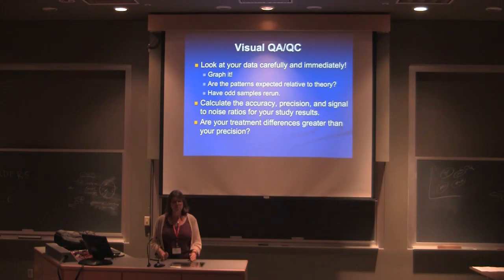Don't let it pile up, particularly if you're running your own samples and you get to be on the mass spectrometer only for a limited amount of time, and you're burning the midnight oil and you're getting the data off and you're just going to look at it later. And it piles up and piles up, and then finally you're all done, you're exhausted, and you go look at your data and it's like, oh no. We really should have done some maintenance. The machine was not working well, all the weighing that I did, all the midnight oil, it was a waste because the data was no good.